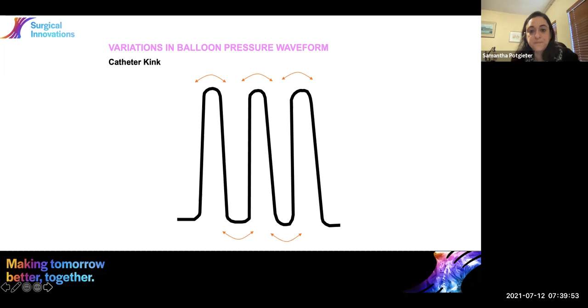So remember we spoke about a relative contraindication on the balloon pump therapy if your patient has such severe PAD that the doctor may struggle with insertion. It can be that your positioning is incorrect or that the catheter, with this very bad insertion, has in fact kinked, and you are looking at this rounded curve that you see here, which isn't typical for the sharp V that we normally get with the balloon catheter when you look at its waveform on the console. And that just means that either your position is incorrect and the catheter isn't actually sitting in the correct position in the aorta, or it can actually mean that the catheter has kinked itself. And then you typically get that look.